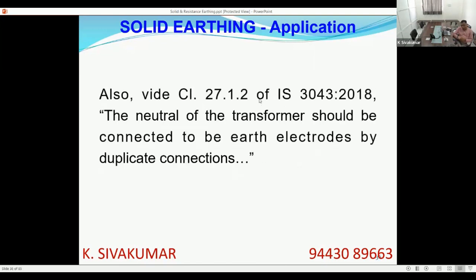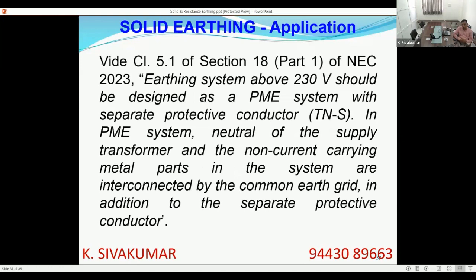And in IS 3043 also, 27.1.2 says the neutral of the transformer should be connected to the earth electrode by duplicate connection. That means solid connections. Then NEC, National Electric Code 2023, Section 18, Clause 5.1, Part 1: earthing system above 230 volts should be designed as a protective multiple earthing system with a separate protective conductor, TN-S.